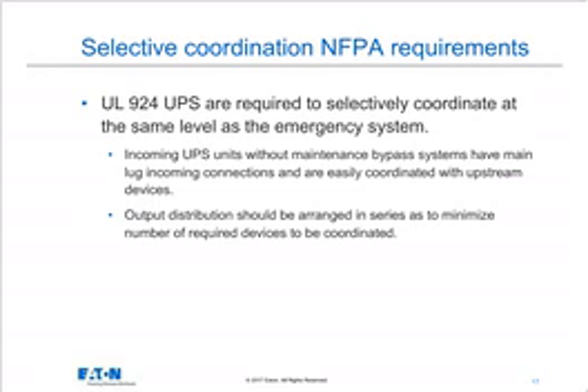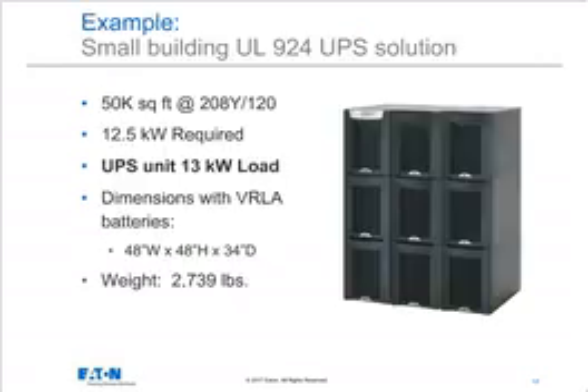Here's an example for a small building, let's say 50,000 square feet or less. Now in a building like this, the lighting voltage is likely to be 120 volts, just like in your residence. So for 50,000 square feet, roughly a 12 kilowatt UPS would be required, and that's what we show in the picture here as an example. This particular example is about 48 inches wide, 48 inches tall, and 34 inches deep. Notice the weight here, over a ton of battery here for a 50,000 square foot building.